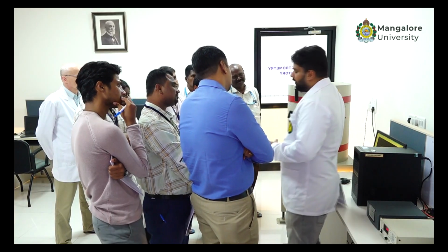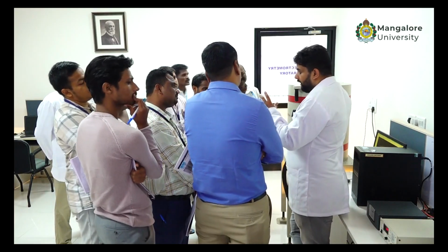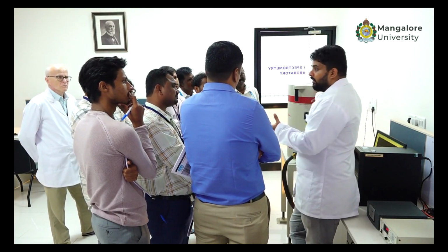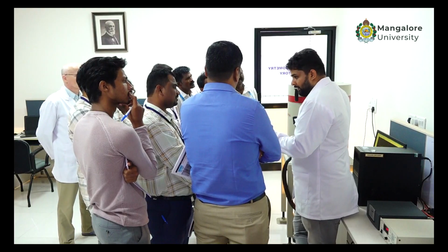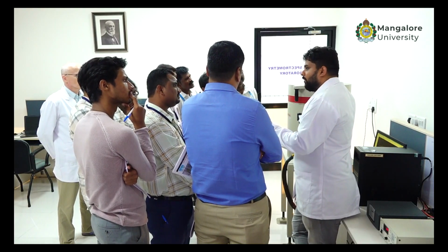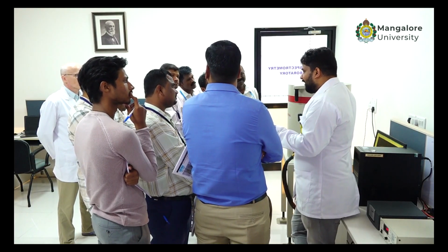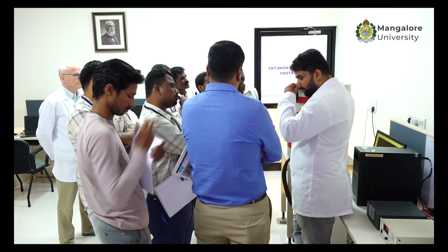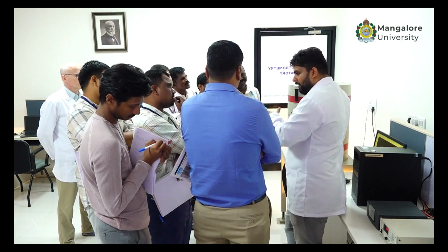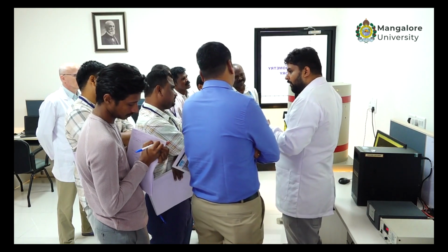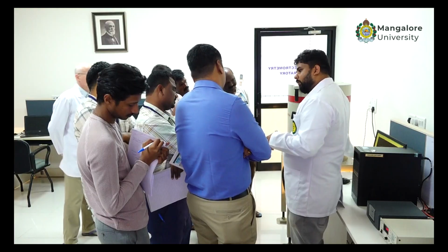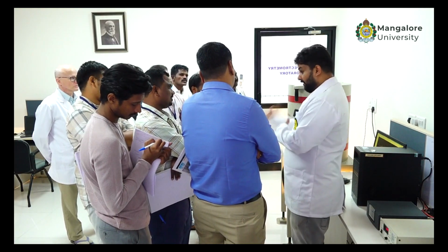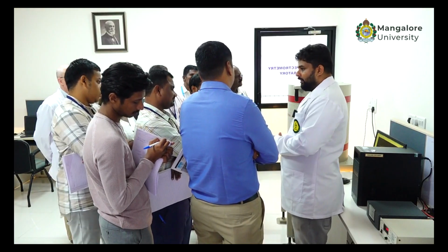The high purity germanium detector depends upon your window. We have a carbon window which can start detecting from 30 kilo electron volt. If you have an aluminum window, I think it is 100 keV, something like that. And then there is another composite window, which again will give some other energy. We have the best one, the carbon window, which starts counting from 30 kilo electron volt. Anything below that you cannot detect by HPGe, at least by this HPGe. I don't know if there is any other HPGe that can detect lower than that.